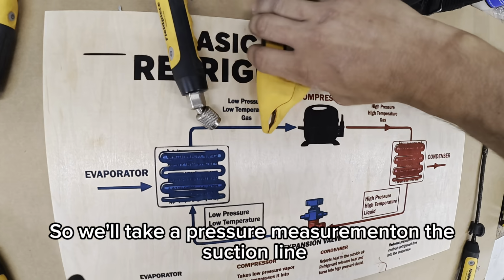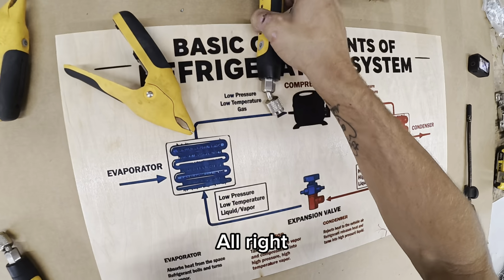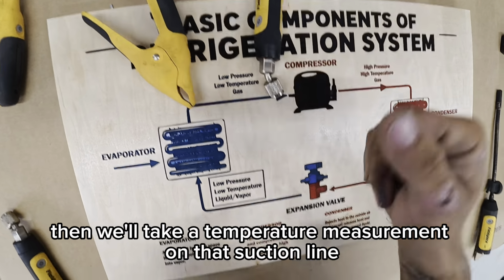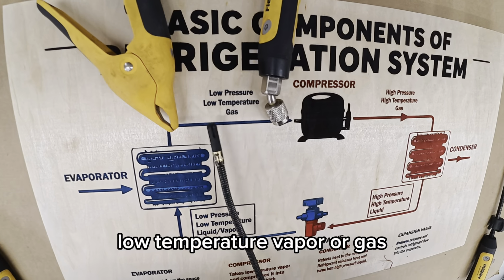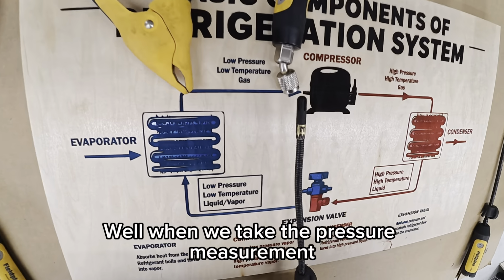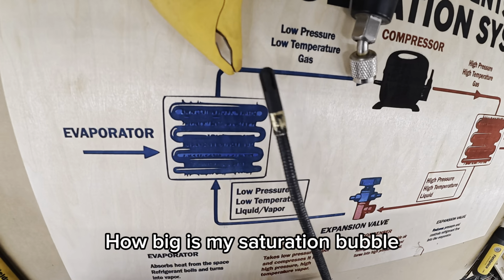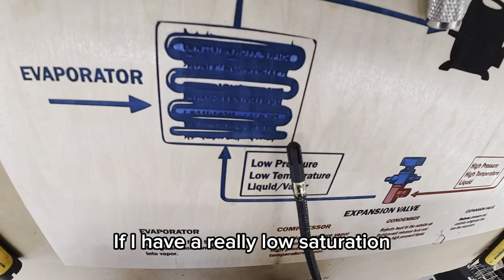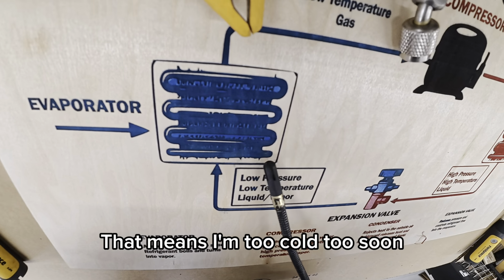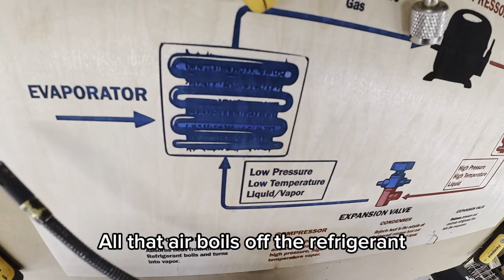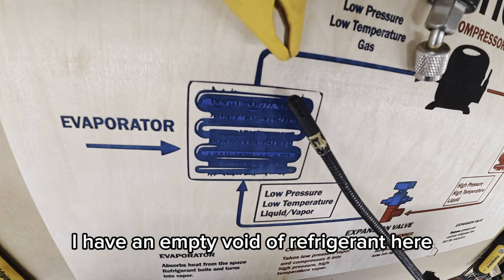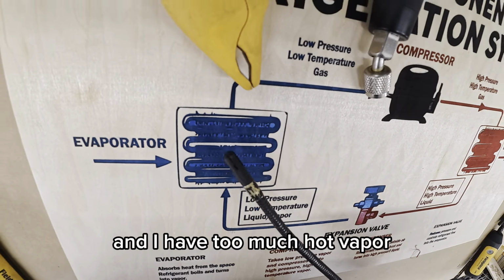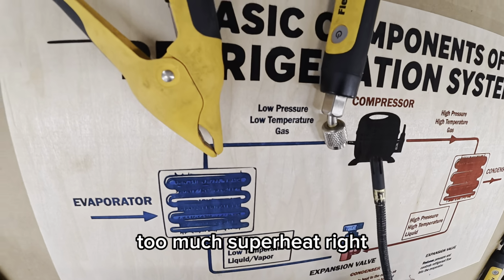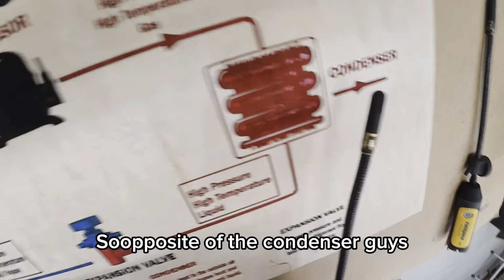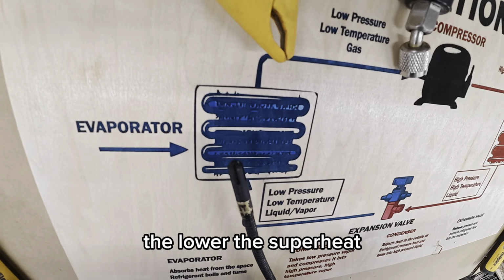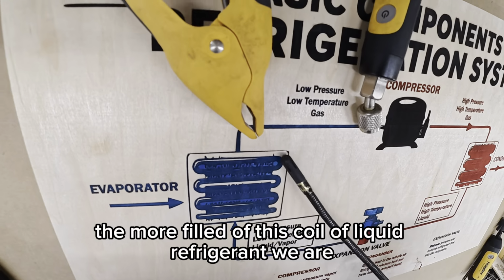So we'll take a pressure measurement on the suction line, right? And then we'll take a temperature measurement on that suction line. And we're going to see a low pressure, low temperature vapor or gas. Well, when we take the pressure measurement, that tells us how big is my saturation bubble. If I have a really low saturation, my saturation bubble's tiny, right? That means I'm too cold too soon. All that air boils off the refrigerant. I have an empty void of refrigerant here, and I have too much hot vapor, too much superheat, right? So, opposite of the condenser, guys, the lower the superheat, the more filled of this coil of liquid refrigerant we are.